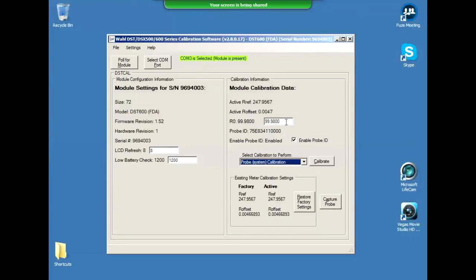These units have a serial number in them, or probes. If you're using a cable under 30 meters, I think it is, then there's a serial number chip built into the probe, and that's what this number here is. That's a unique number. The company that makes the chips automatically programs that number in, and it can't be changed. So in this case, our probe and meter are tied together. If I was to hook another probe up to this meter, it would just give me an error on the screen over here. It would say PRB, which indicates to me that I've got the wrong probe hooked up.